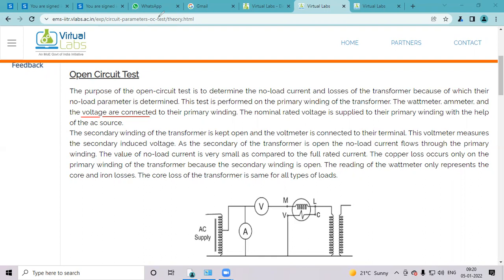And the power requirement for this no load condition is nearly equal to the no load losses. Whatever no load losses are there, that much power is taken to overcome them. The open circuit test is used to determine the no load current, and once the no load current is determined, we are able to calculate the no load losses of the transformer.